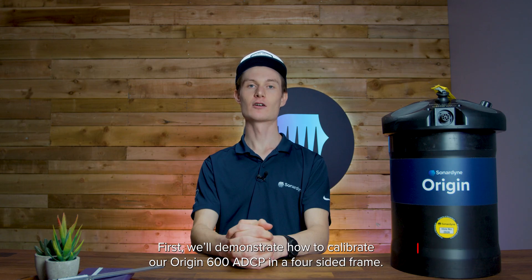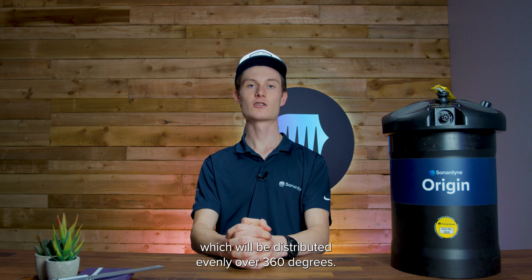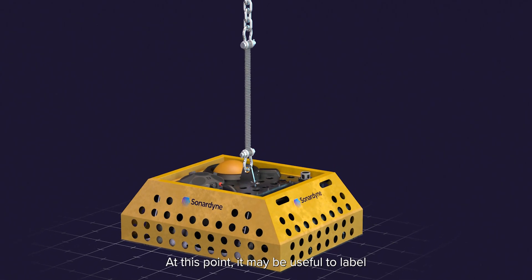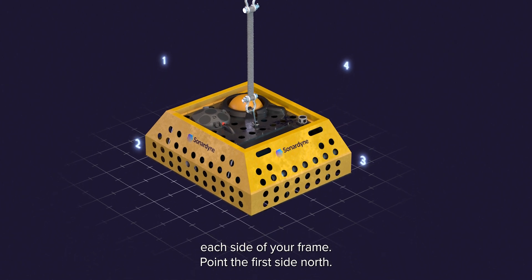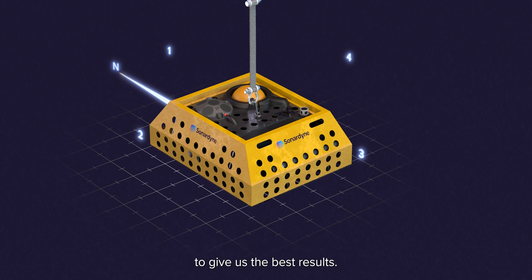First we'll demonstrate how to calibrate our Origin 600 ADCP in a four-sided frame. Before we start, we'll need to set our four main headings which will be distributed evenly over 360 degrees. At this point, it may be useful to label each side of your frame. Point the first side north.